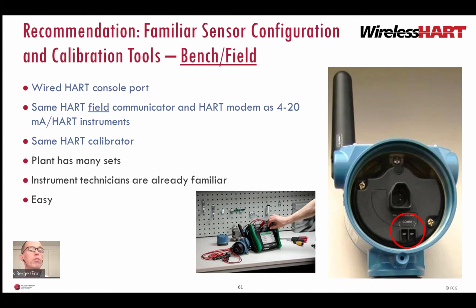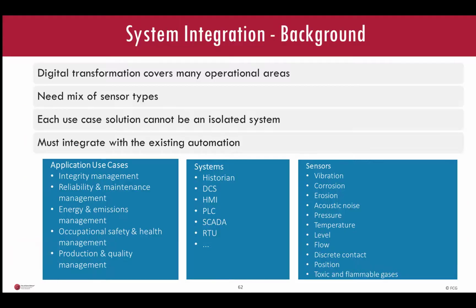Because it's the same portable tools used for all WirelessHART sensors, regardless of manufacturer, and the same familiar tools instrument technicians are already using for wired instrumentation. The procedures for WirelessHART sensors are almost the same as for the 4 to 20 milliamp HART sensors. Calibrators don't support other wireless sensors. Digital transformation of reliability, sustainability, safety, and production work practices as part of Industry 4.0 require all kinds of advanced sensors. The plant will have wireless sensors from multiple manufacturers.